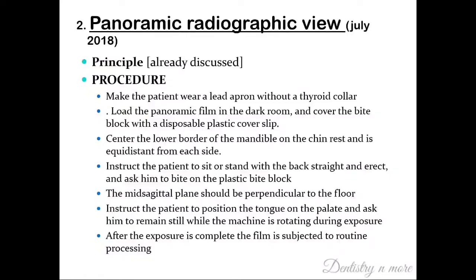That is, the patient is asked to wear a lead apron without the thyroid collar, and load the panoramic film in the darkroom and cover the bite block with a disposable plastic cover slip. Center the lower border of the mandible on the chin rest and at an equidistance from each side.